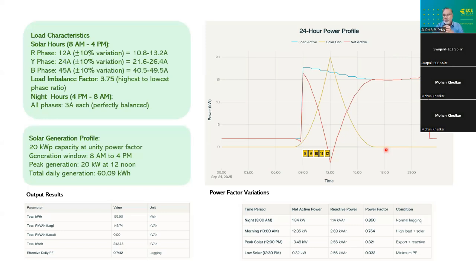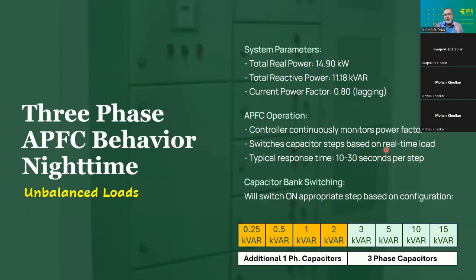problems in the grid is very tough in single phase, in case of three phase consumer about 20 kilowatt with most of the single phase loads. Okay. So what do we do? Actually, solution is very simple. You go for static var generator and your problem will be addressed.